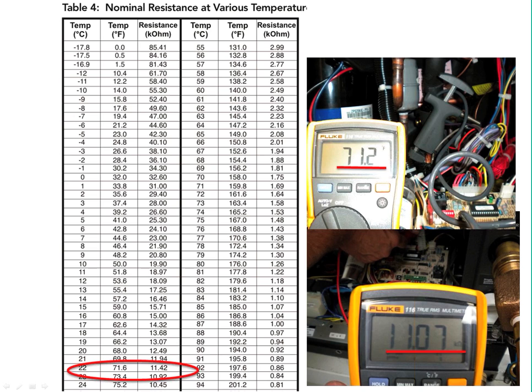If you want to double check, if you still have some concerns, you may want to consider doing an ice bath, disconnecting that thermistor and dropping it into a glass of water with ice, and give it another temperature range check, again using additionally your Fluke or other multimeter measuring device, and do it in a different temperature range. So that's thoroughly testing the thermistor to make sure that that indeed is the issue.